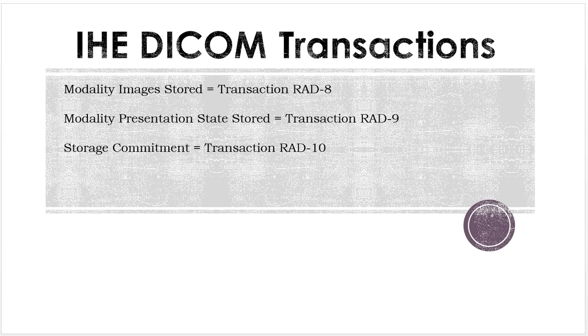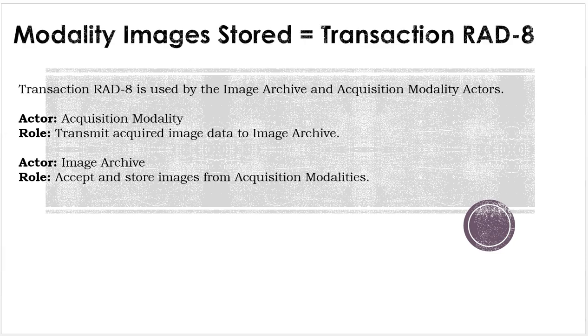Now let's talk about some IHE DICOM transactions. Modality images stored is transaction RAD-8. Modality presentation state stored is transaction RAD-9. And storage commitment is transaction RAD-10. Transaction RAD-8 is used by the image archive and acquisition modality actors. The acquisition modality transmits the acquired image data to the image archive, and the image archive accepts and stores images from acquisition modalities. Simply put, the CT scanner acquires the images and sends them to PACS, and PACS accepts and stores the images.